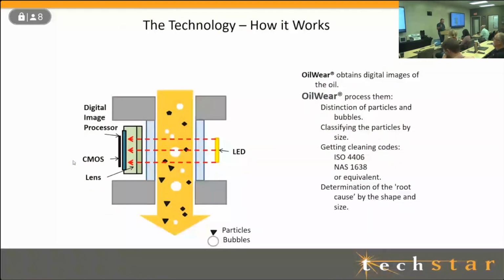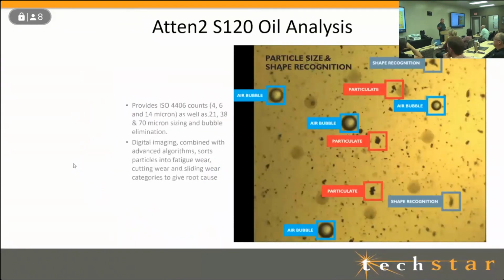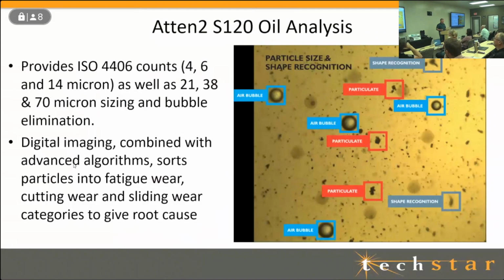We'll touch a little on the technology of how it works. As you can see, the oil is basically passing through the sensor. There's an LED light that is illuminating the sensor, and basically a digital image processor. A good way to look at it would be like a microscope. So it's basically a continuous microscope with a flow of oil through it, and it's continuously analyzing the particle counts through that sample. As these particles come through, it's able to classify the sizes, but more importantly, the shapes of the particles. That's really the secret sauce of these guys. That database of image files and everything is built internally. So no need for it to go to a computer system to be analyzed and then give you a report out.